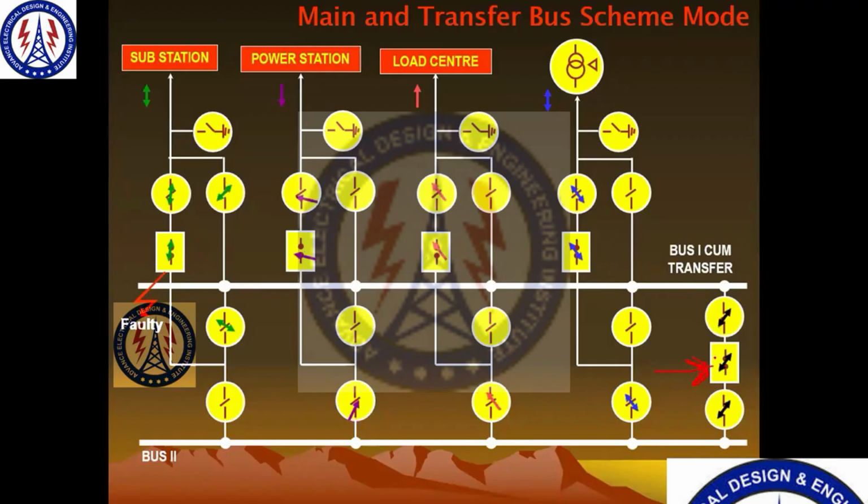Yes, yes. If this circuit breaker fails, how come this is a reliable system? See, there are cascading faults. There is already a fault here. If again there is a fault, again there is a fault. Multiple faults will not happen at the same time in the system. A fault occurring here, then a fault occurring here, then a fault occurring in every part: it is not happening like that, after 5 seconds or so. When a fault occurs, within 100 milliseconds or 30-40 milliseconds it will be cleared. Your circuit breaker will be tripped within a millisecond.